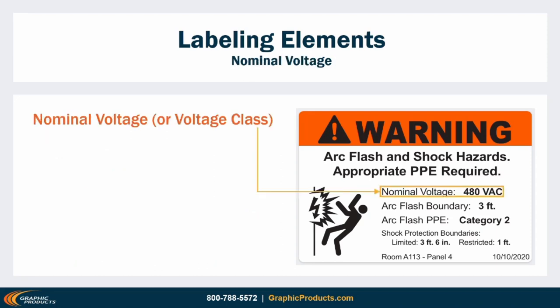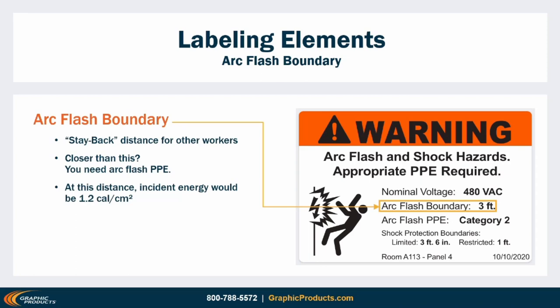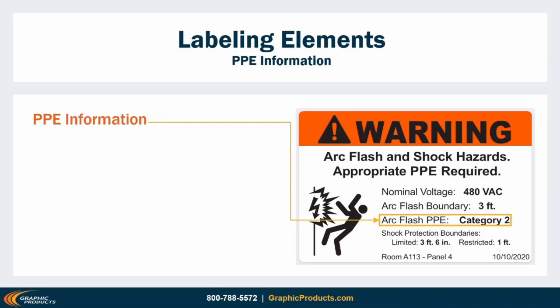First, there's the nominal system voltage — the voltage class for the equipment. This is usually the easiest detail to track down and serves as a quick indicator for the power of a system. Next, there's the arc flash boundary — the stay-back distance, how far away other workers should stay when work is being done on the equipment. Anyone who gets closer needs PPE to protect them from the blast of heat from a potential arc flash. This boundary is defined as the distance where incident energy from an arc flash would be 1.2 cal/cm², representing when unprotected people are likely to get second-degree burns. Crossing this boundary triggers the requirement for PPE to protect against burns.